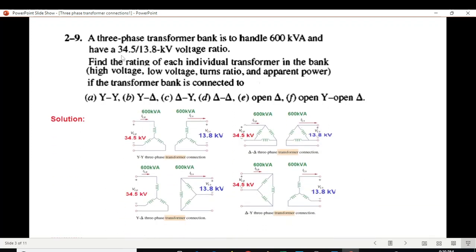The different connections are YY, Y-delta, delta-Y, delta-delta, open delta, and open-Y open-delta. Let's incorporate the given values into all four basic circuits. The primary voltage is 34.5 kV — remember, voltages given are always line-to-line. The secondary side is 13.8 kV, also line-to-line. The power is 600 kVA on both primary and secondary sides.